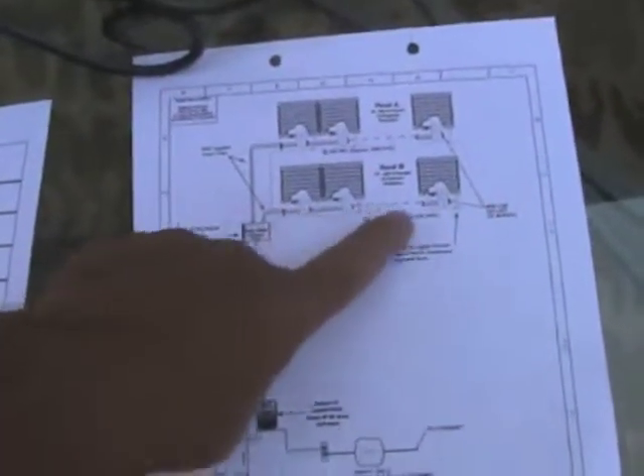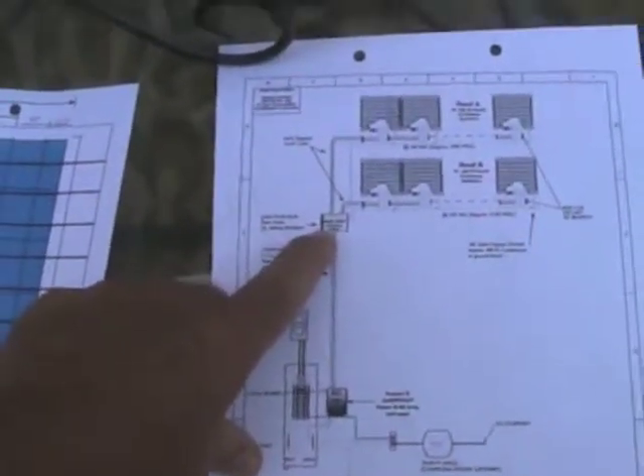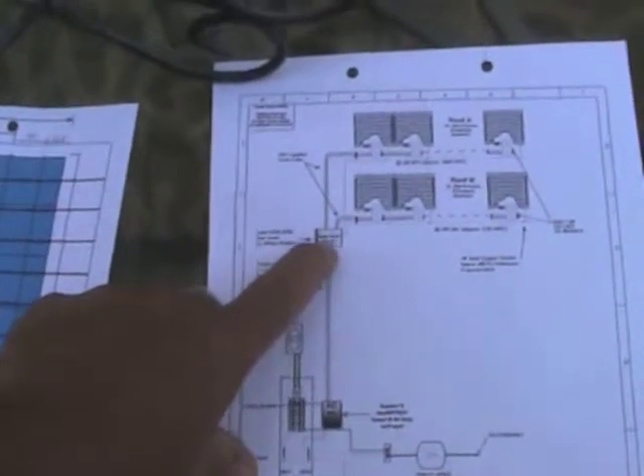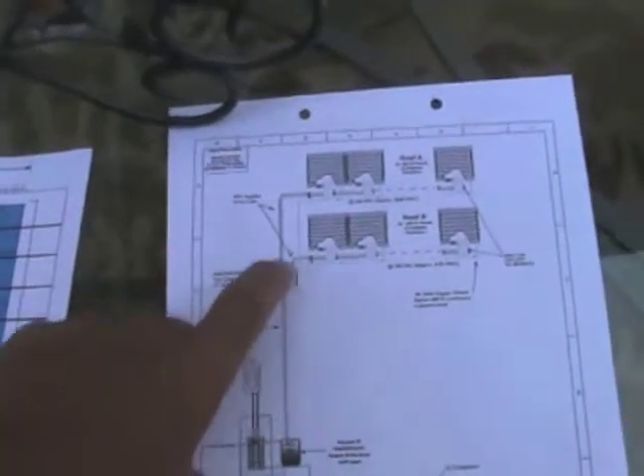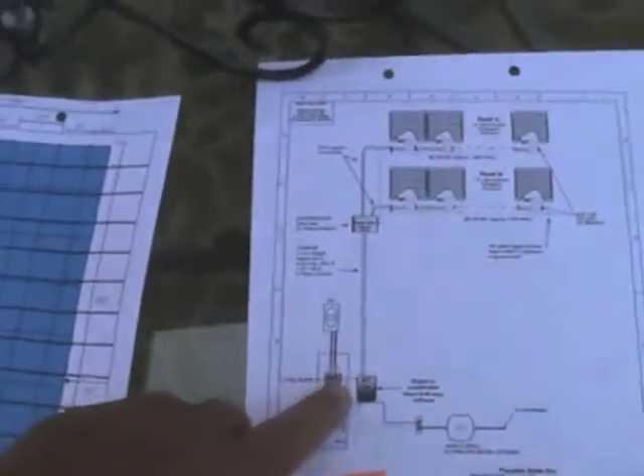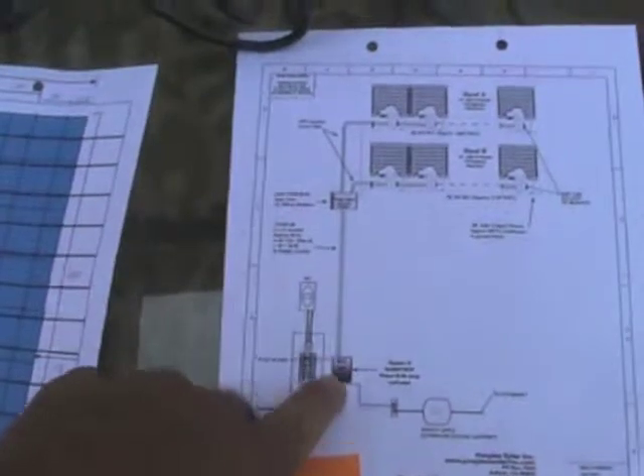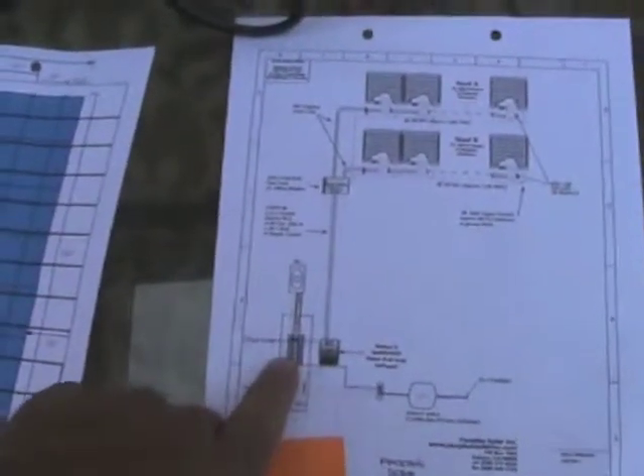These are in-phase inverters into a solar deck combiner, basically, with two 20 amp breakers, and those 20 amp breakers are just some extra protection. You can open this box up and turn them off so you can service them from the roof if necessary. And you can see that feeds down, in this case, a number 8 THHN wire, single phase, so there's 3 wires coming down and to the AC disconnect, and then directly into our panel.